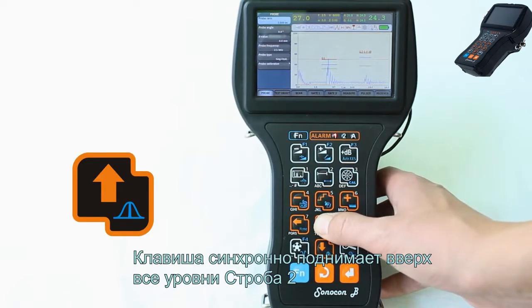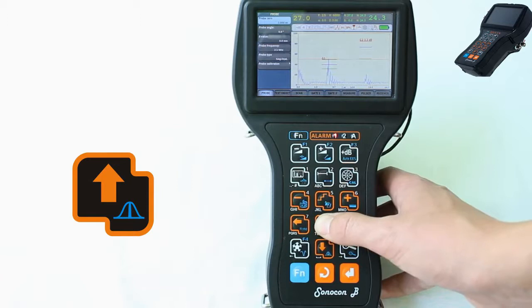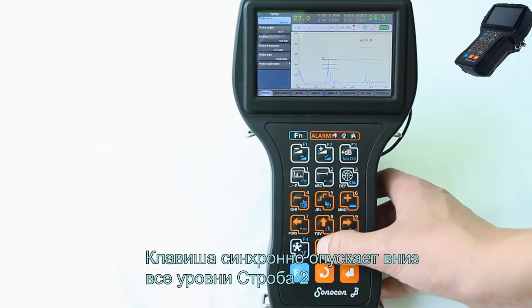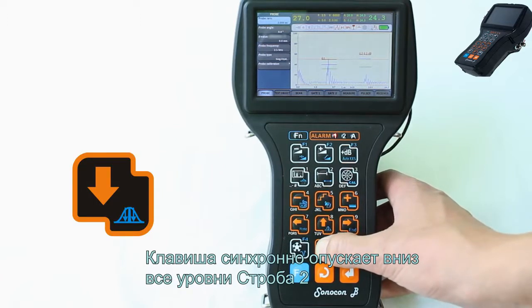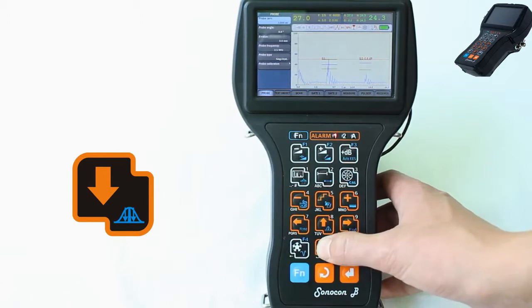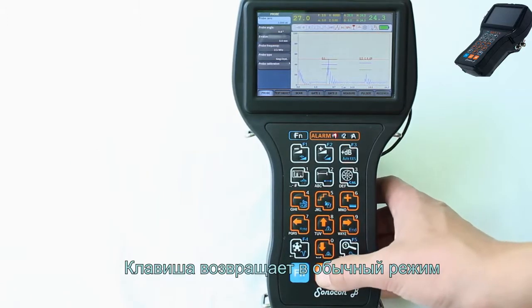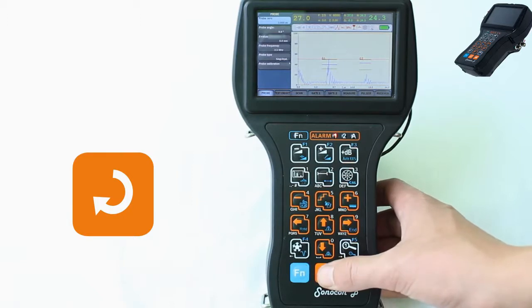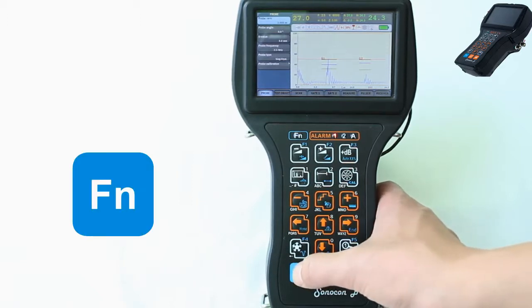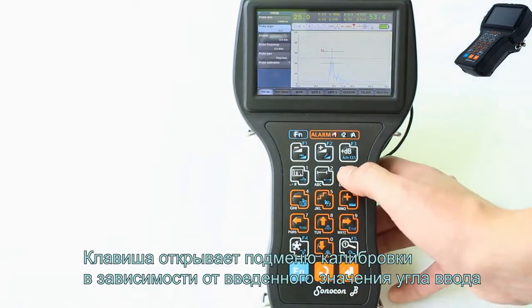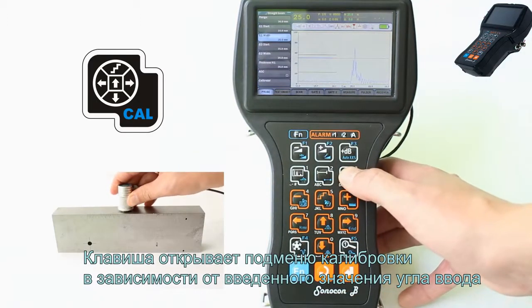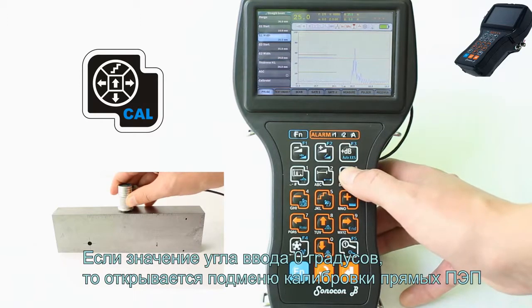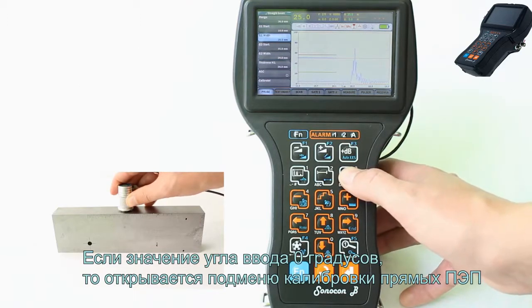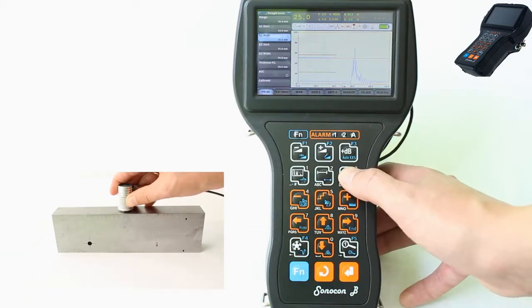This button simultaneously lifts up all levels of gate 2. This button simultaneously moves down all levels of gate 2. This button returns the instrument to the normal mode. This button opens the calibration submenu depending on the input value of the probe angle. If the value of the probe angle is 0 degrees, the calibration submenu of straight beam probes is opened.